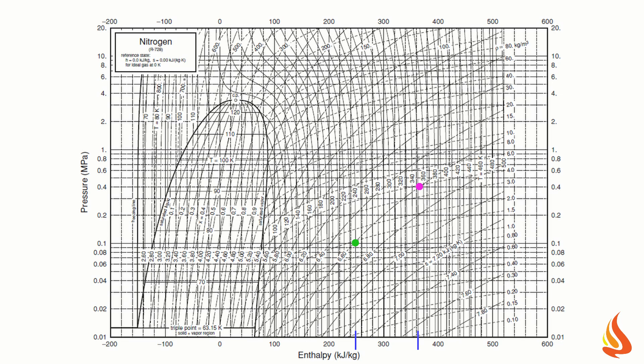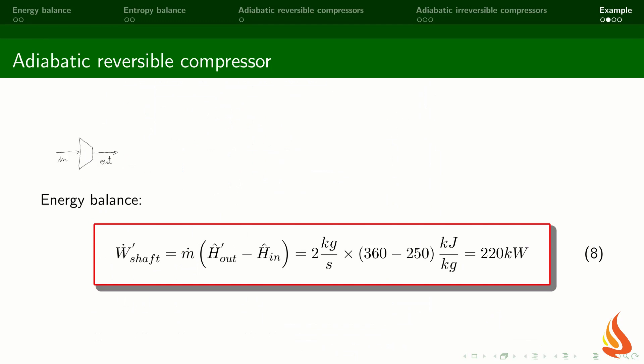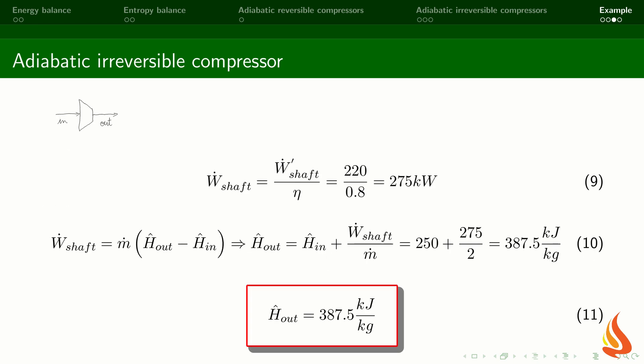The reading locations are identified by the small blue vertical bars on the enthalpy axis. Using these specific enthalpy values and the mass flow rate, we find that the power of the adiabatic reversible compressor is 220 kW. We now divide this value by 0.8, which is the efficiency, and find that the power of the adiabatic irreversible compressor is 275 kW.